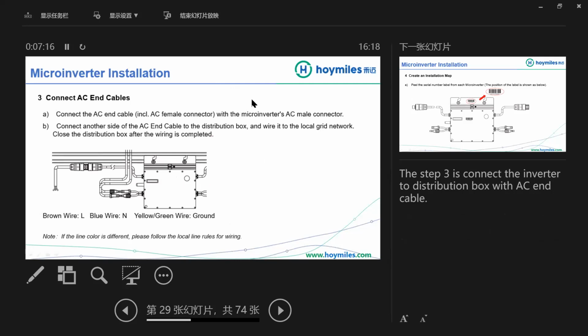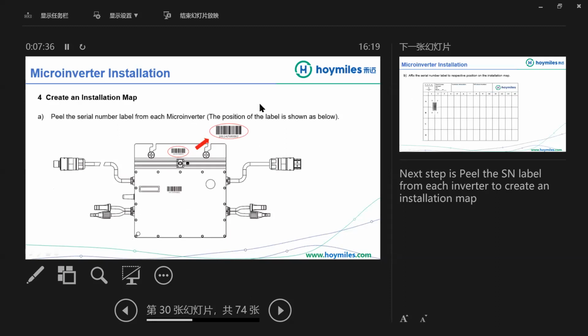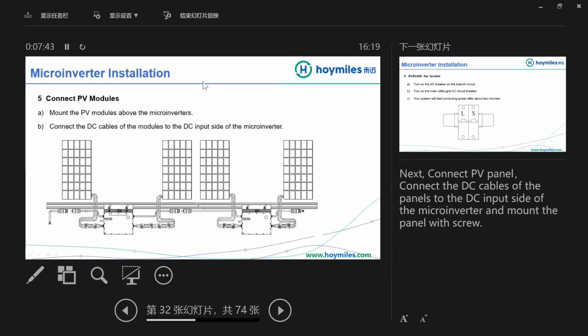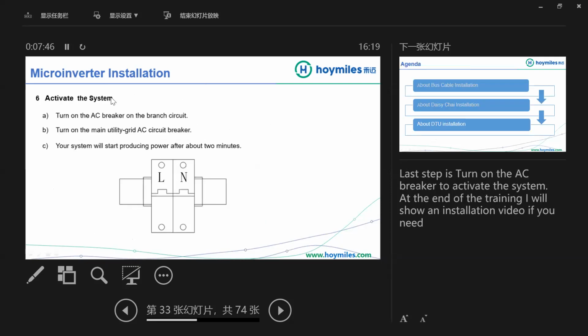Then connect the AC end cables. Connect the AC end cable with the microinverter's AC male connector. Then connect another side of the AC end cable to the distribution box and wire it to the local grid network and close the distribution box after the wiring is completed. The following installation steps is same as the bus cable installation. Create an installation map, connect the PV modules, then activate the system, and everything is done.